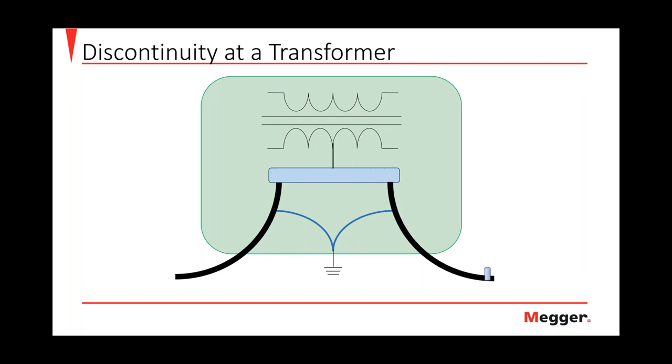then back out. And now what we're going to see is we have this large degree of separation between the center conductor and the concentric neutral or tape shield braid at that point. So if it's measuring that impedance between the center conductor and that braid, as that distance increases, the impedance increases. So as they begin to come back together, we show a decrease in impedance. And that gives us that wiggle waveform, that signature that we see on the TDR trace. We see that separation and then where it comes back together and where it balances back out at the end.